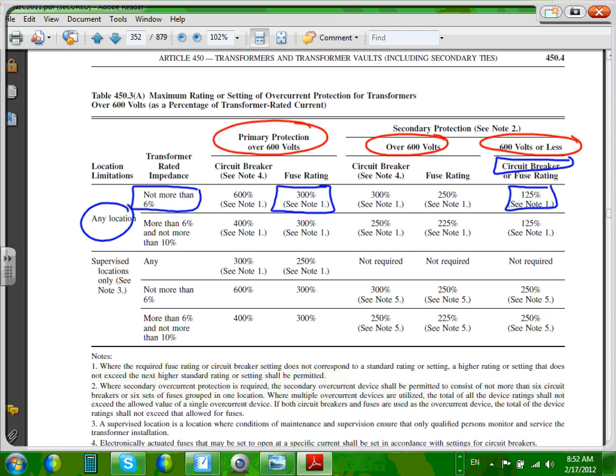Note. Here, there's a note number 1. Do you guys remember what note number 1 says? If you don't hit the standard, what do you do? Go up. If you can't go up, what are you going to do? You have to go down. So if you don't have note number 1, then if you don't hit the standard, you have to go down. And we all know where to find the standard. 240.6. We will be using this table, guys, for a lot of calculation. Any question about this table?